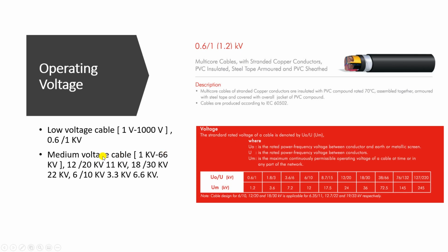Now, medium voltage ranges from 1 kilovolt up to 66 kilovolt. Some of the cables used are 12/20 kilovolt. Cables such as 12/20 kilovolt are used in an 11 kilovolt network, a medium voltage network. The 18/30 kilovolt can be used in the 22 kilovolt network. 6/10 can be used in a 3.3 kilovolt or 6.6 kilovolt network. Again, these are the operating voltages of the network itself: 3.3, 6.6, 11 and 22 kilovolt. All of these are the voltages of our network.